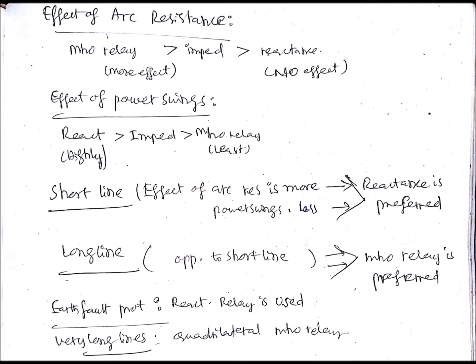The mho relay is going to get affected the most by arc resistance, then comes the impedance relay, and then comes the reactance relay. For the reactance relay there is no effect of arc resistance, which is very desirable. So the mho relay is affected most by arc resistance.